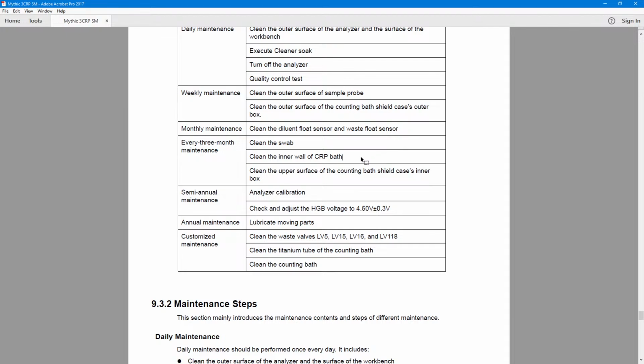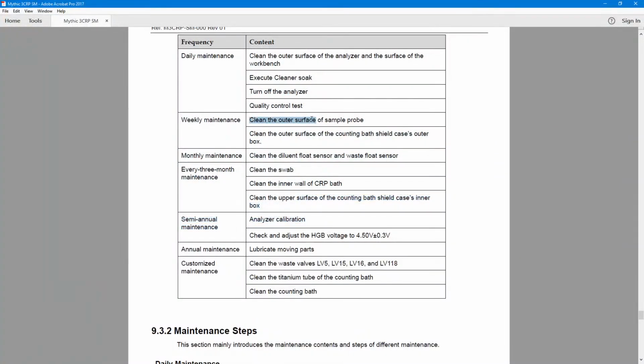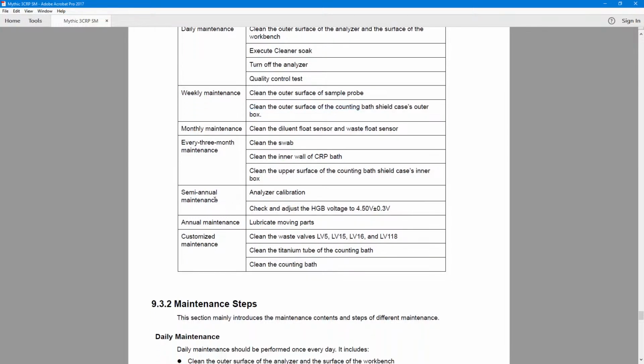Usually, if there is something, it will be on the top of the CRP bath. Clean the upper surface of the counting bath shield case inner box. So it's the same thing as here. It's the same. Every 6 months, we recommend making an analyzer calibration, and in this case, we recommend calibrating the hematology part and the CRP part every 6 months.